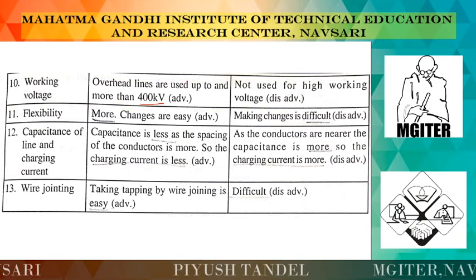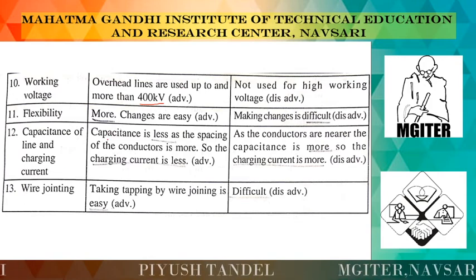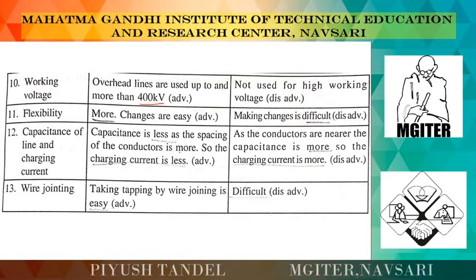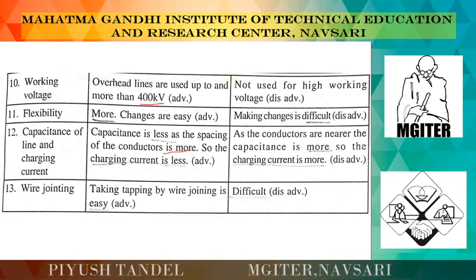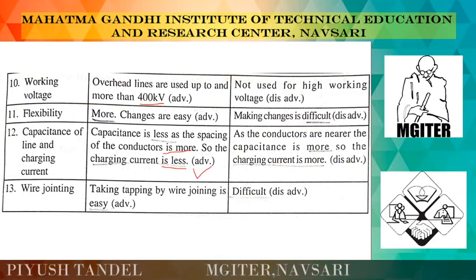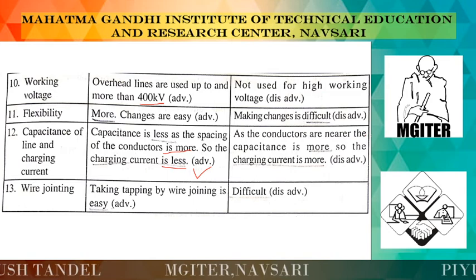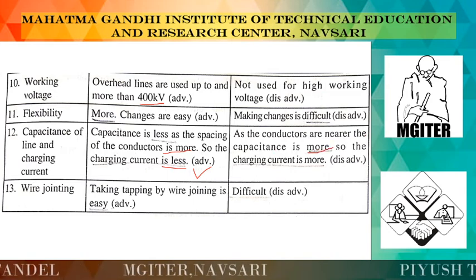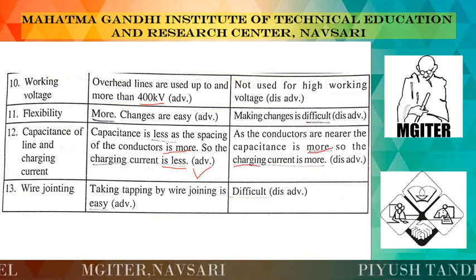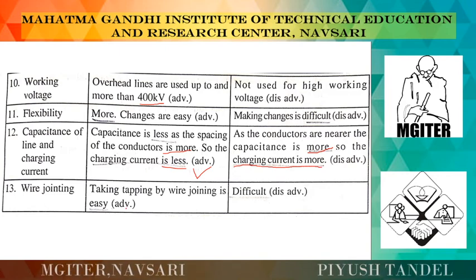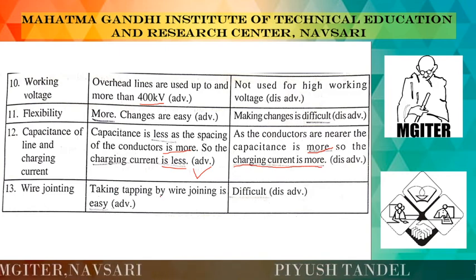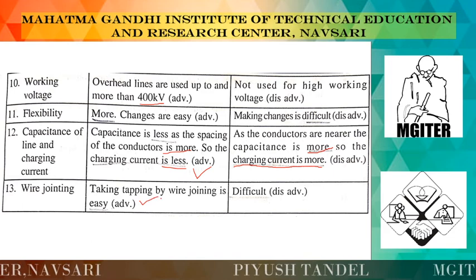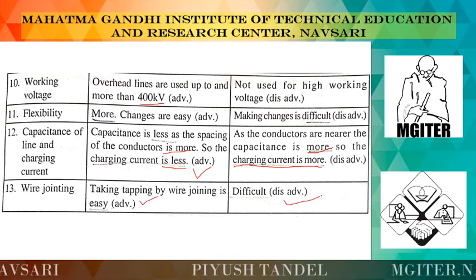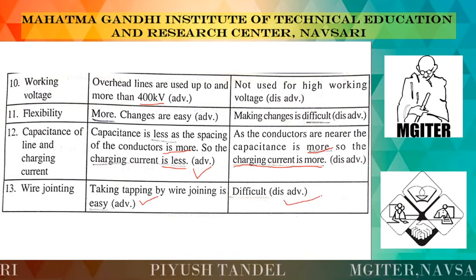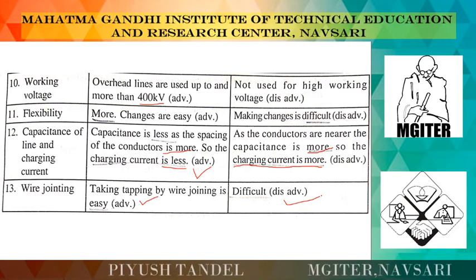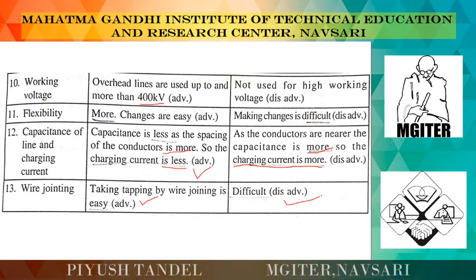Now, the capacitance of the line and the charging current. Capacitance is less as the spacing of the conductors is more, so the charging current is very low, and that is the advantage. As the conductors are nearer, the capacitance is also more, so the charging current required for the underground cable is more. Taking a tapping by wire joint is very easy, and it is very difficult for the underground system. So this is the difference between the overhead system and the underground system.